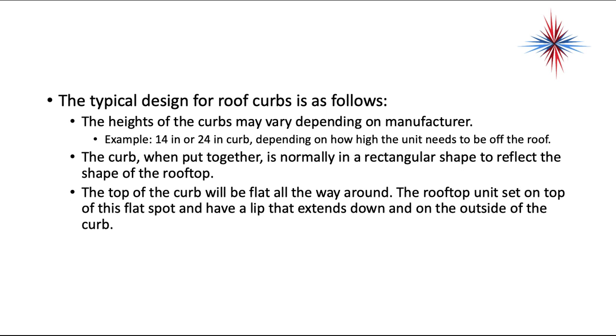The typical design for a roof curb is as follows. The height of the curbs may vary depending on the manufacturer. For example, you might have a 14-inch or a 24-inch curb, depending on how high the unit needs to be off the roof. The curb, when put together, is normally in a rectangular shape to reflect the shape of the rooftop. The top of the curb will be flat all the way around. The rooftop unit sets on top of this flat spot and has a lip that extends down and around the outside of the curb.